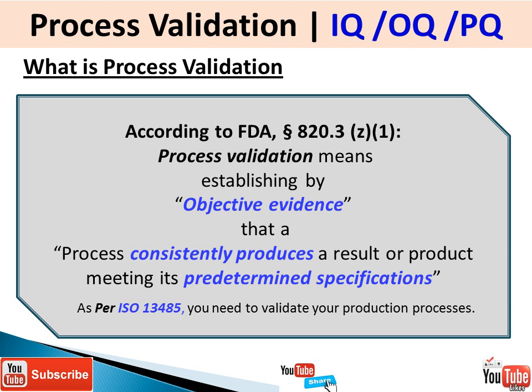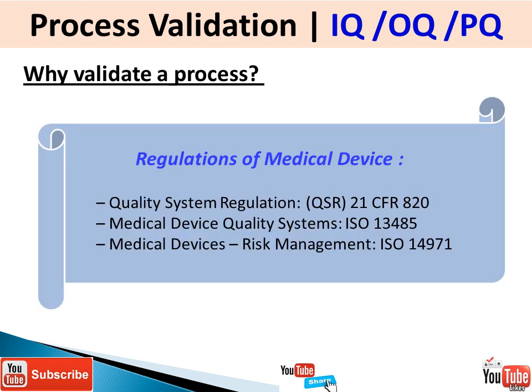Predetermined specification basically refers to your product specification or process specification that, if met, results in a product that meets your customer's needs and intended use. Process validation is a requirement per ISO 13485 — you need to validate your product processes. Validation is only required for processes whose output cannot be fully verified by subsequent inspection and testing. Conversely, if you can fully verify your process output, you do not need to validate the process.